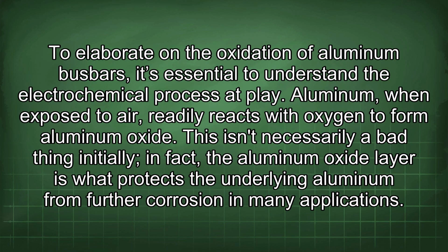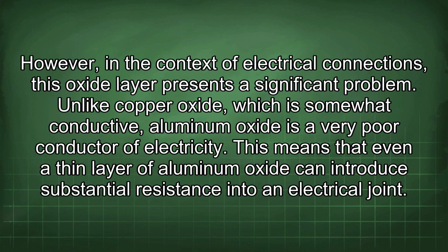To elaborate on the oxidation of aluminum busbars, it's essential to understand the electrochemical process at play. Aluminum, when exposed to air, readily reacts with oxygen to form aluminum oxide. This isn't necessarily a bad thing initially. In fact, the aluminum oxide layer is what protects the underlying aluminum from further corrosion in many applications. However, in the context of electrical connections, this oxide layer presents a significant problem. Unlike copper oxide, which is somewhat conductive, aluminum oxide is a very poor conductor of electricity. This means that even a thin layer of aluminum oxide can introduce substantial resistance into an electrical joint.